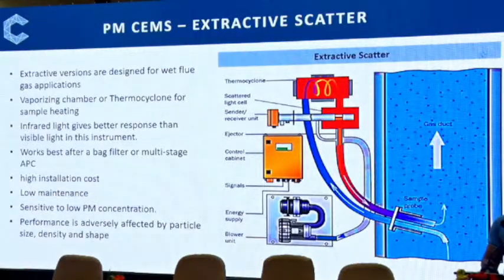This is the one thing that you are going to face pretty soon when you have an FGD. This is the extractive type. Scatter we learned, forward, backward. But when you have FGD, wet type or seawater, moisture content will certainly increase, temperature will go down, and you will have running water in that. You saw one example in this stack. What will you do? The monitors that you have already installed, opacity, forward scatter, backward scatter, will not work. Many of them had asked the question. So they have new work orders ready. Not today, but tomorrow you have to ask for a new one.